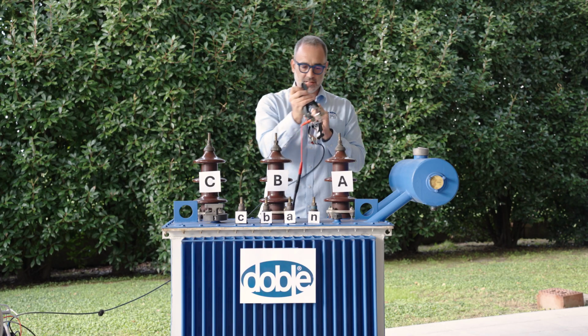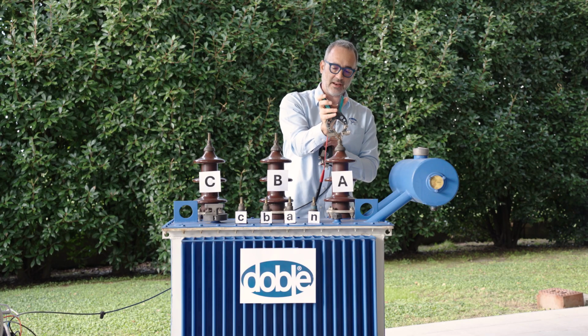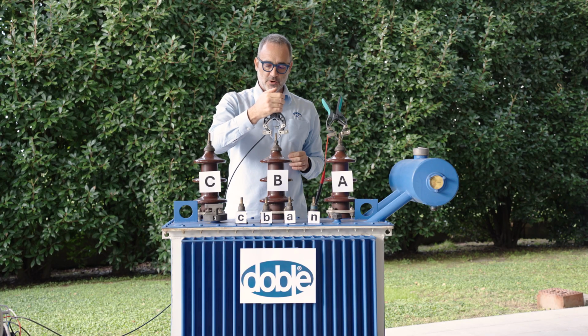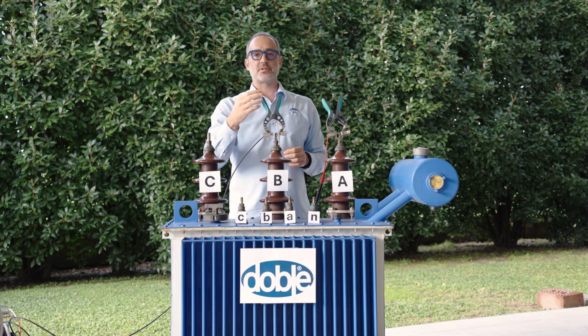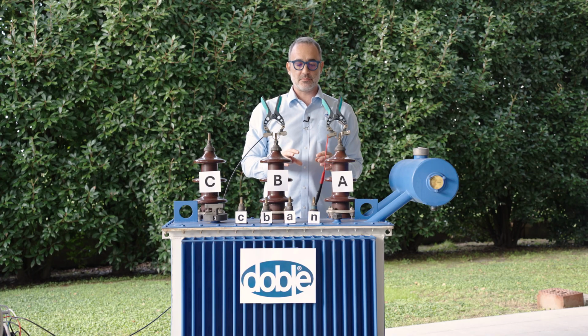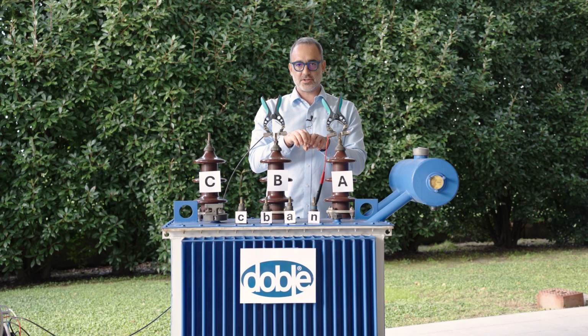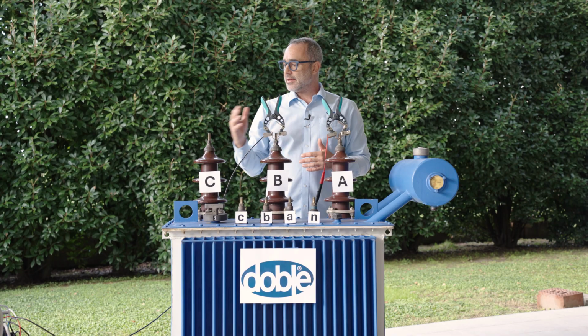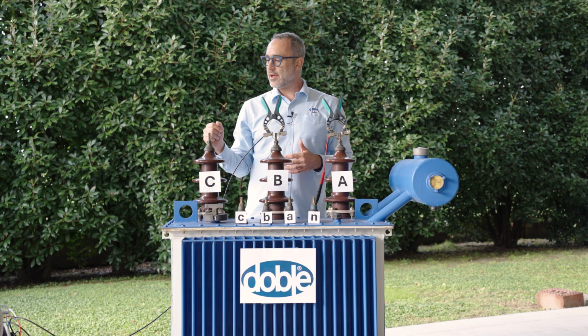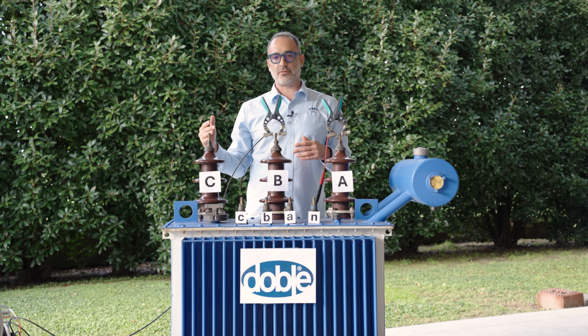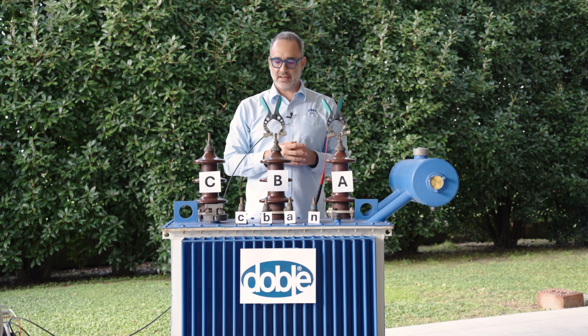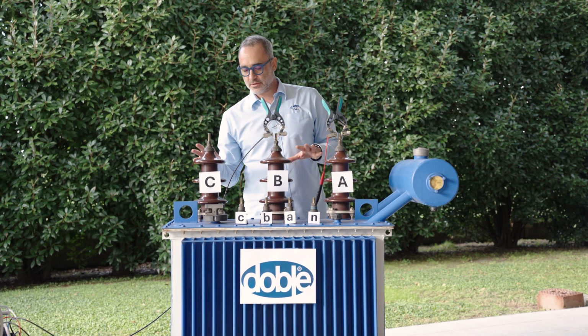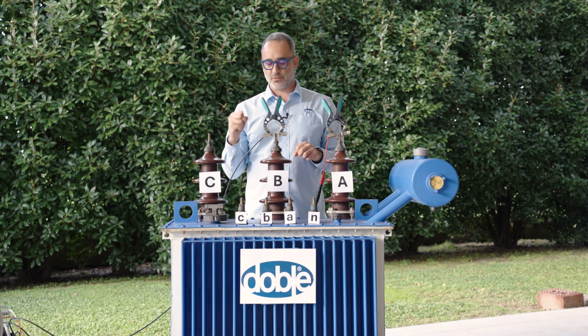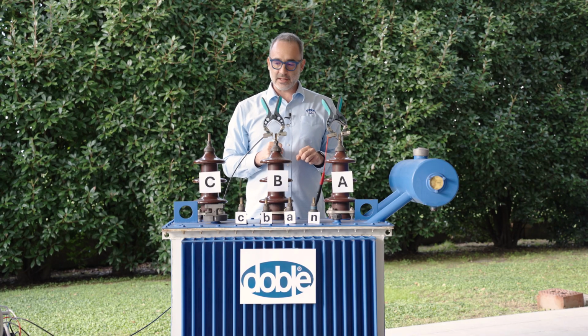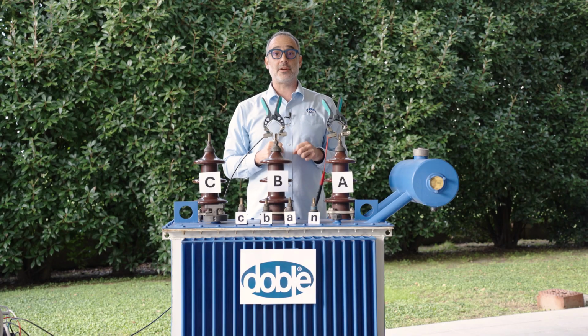Just let me tell you that sometimes if you want to repeat the values which you have in the transformer's report, which was made in the lab of the transformer producer, it might not be possible because they do 3-phase generation and probably at higher voltages. Here we have 2 options. We can generate from STS up to 2 kV, but I'm going to use TD5000 and I will generate voltages higher than that. There should be, to the best of my knowledge, some issues with this transformer's core. So for that reason, let's see what kind of results we will obtain.